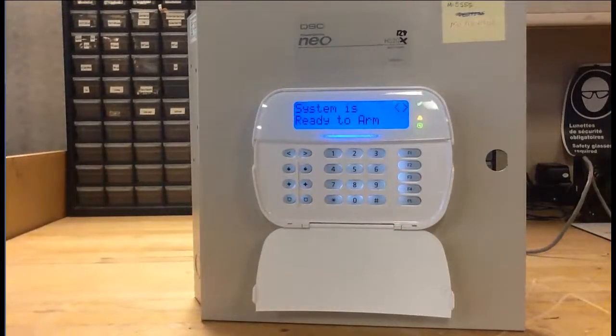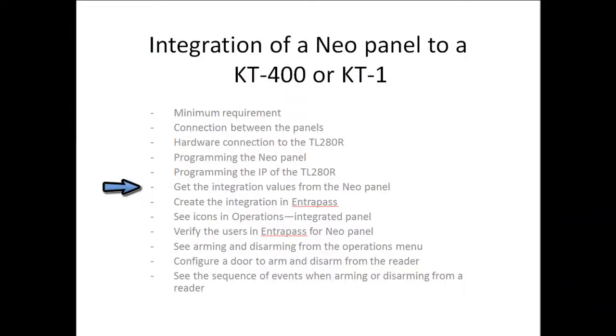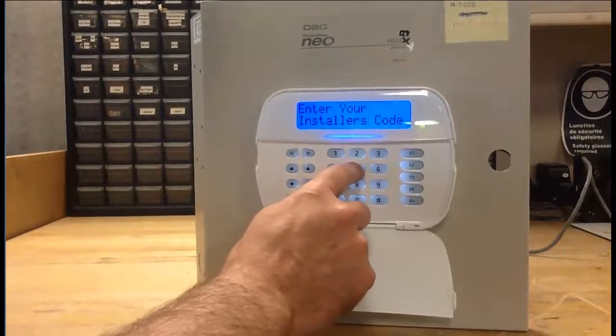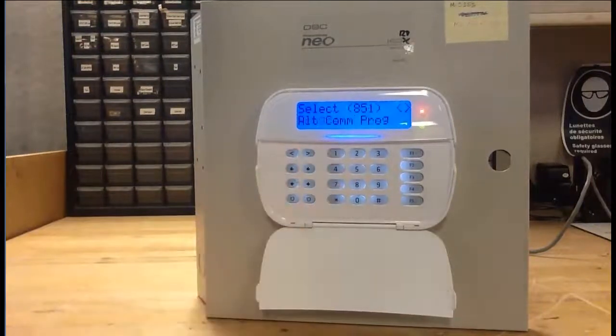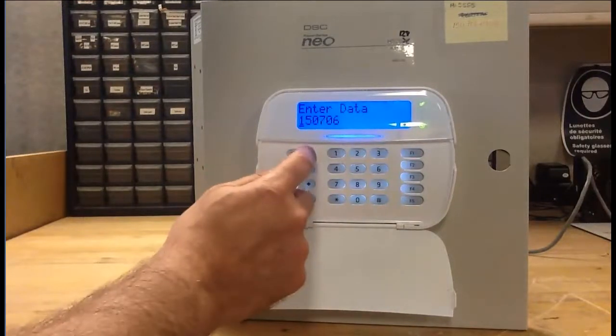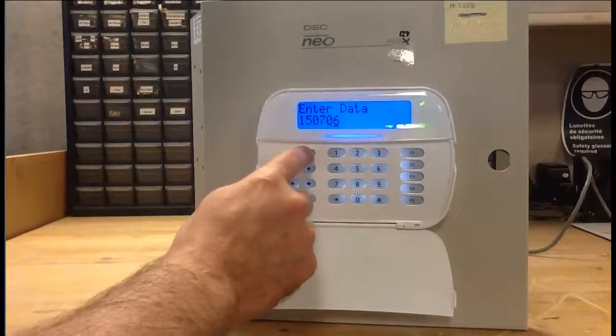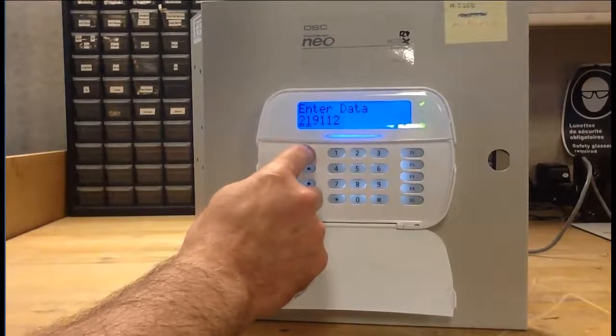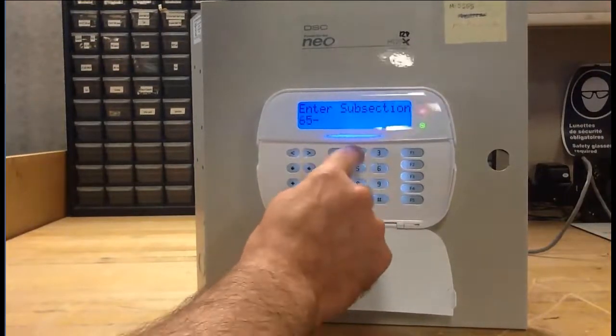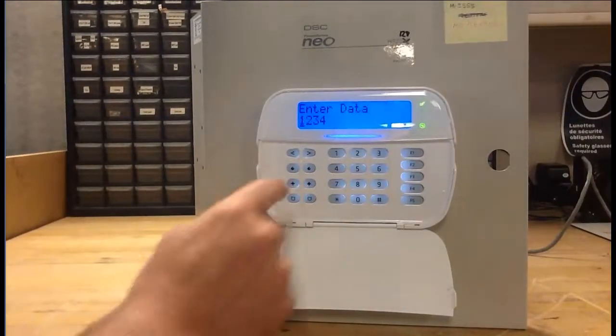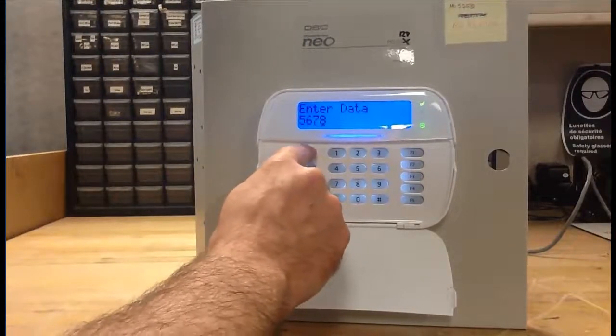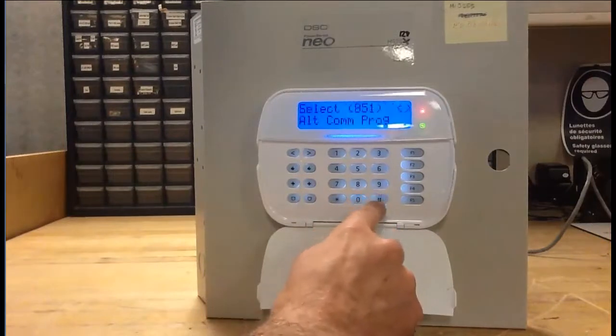Now we're going to take a look at getting the integration values from the NeoPanel. Once again, star 8 and then our installer code 5555. Then we're going to go to 851 and then subsection 651. You can scroll — you'll want to write that number down and scroll to the right to see all 12 numbers. You'll want to write that down because you'll have to enter it in EntraPass later on. Then go to subsection 652 — this time you have 8 characters. You'll want to copy those and make sure you enter the same thing in EntraPass.